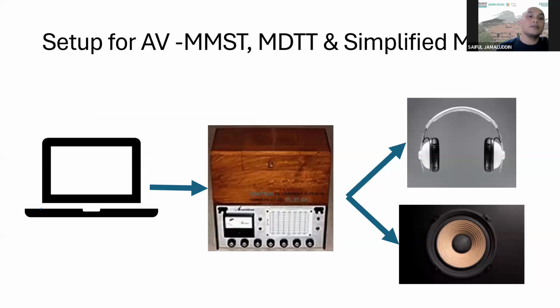However, for the auditory visual Malay matrix sentence test, the digit triplet test, and the simplified matrix sentence test, what you need is a PC to download the software. You need an audiometer, connecting the PC to the audiometer through a 3.5mm cable, male to male, so that you can plug it into the external input of the audiometer, and the output goes out to your respective transducers, your AC and your free field speaker. There's a short calibration process that needs to be done using a calibration tone. As soon as we've done that, then your system should be calibrated already.